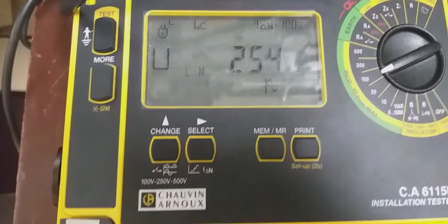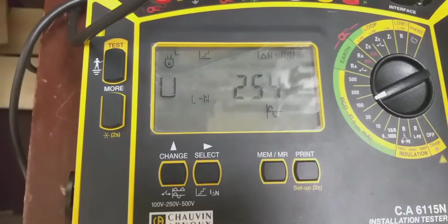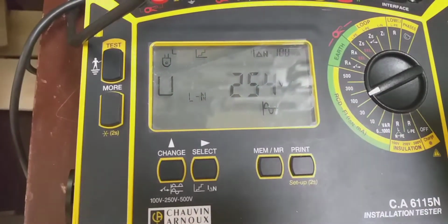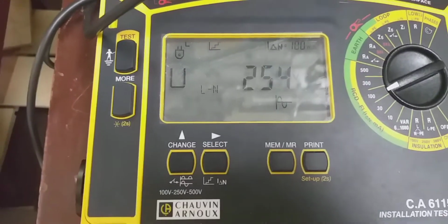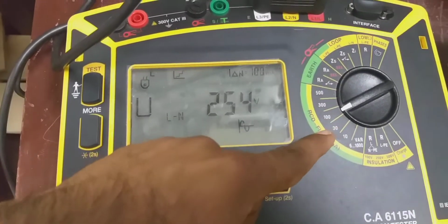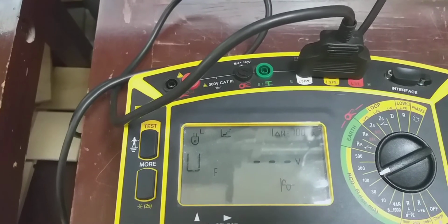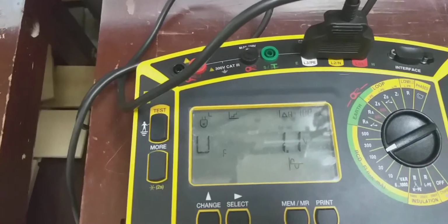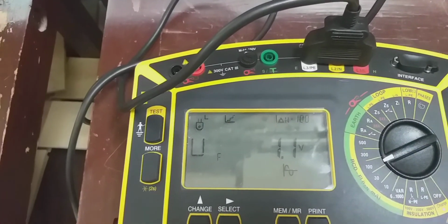So you keep this here in the 100 milliampere test point. So now what we have to do, you can see also here I delta n you have selected 100 milliampere. Suppose your RCD is 100 milliampere and if you have chosen 30 or 300 something like that, that means this device is not going to give you the output. So you have to select the appropriate settings here, and then later you can press the test button. You can see the voltage, that is touch voltage in the installation. So this is 1.1. In Oman it is up to 50 volt is allowed, but here in our installation it is only 1.1. So our installation is very good in the case of touch voltage.